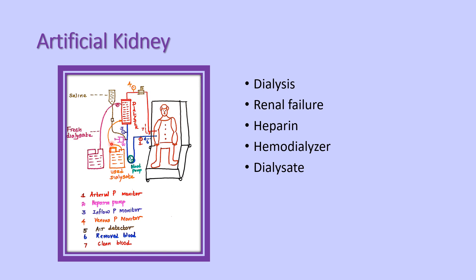The artificial kidney also has many pressure monitors. The first is the arterial pressure monitor, the second is the heparin pump, the third is the inflow pressure monitor, the fourth is the venous pressure monitor, and the fifth is the air detector.